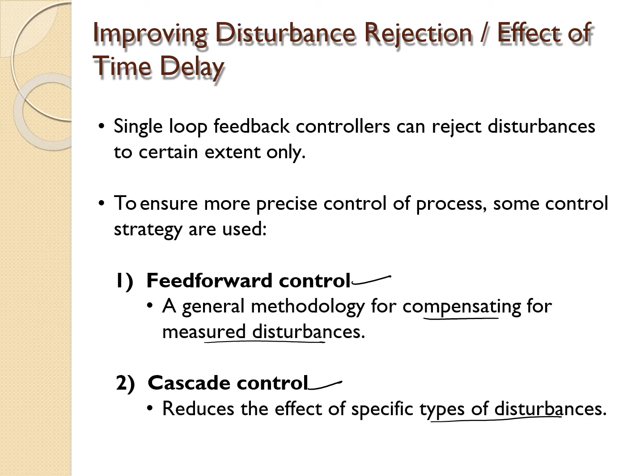Cascade control is used to reduce the effect of specific types of disturbances. Basically, cascade control is one type of advanced control. The simplest one is feedback control, then we have feed forward plus feedback, and lastly cascade control. A feed forward control system is used to compensate for disturbance in the system before it affects the control variable. Remember just now for feedback control, the disturbance will cause the process output to deviate first. After the deviation occurs, then they measure and overcome the deviation using the controller, right? For feed forward, it will remove the deviation first to ensure that the process variable coming out from the process achieves its set point.